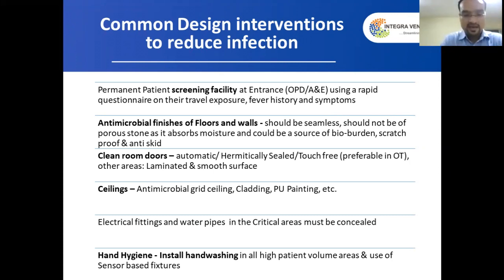Similarly, for ceilings we get a lot of grid ceilings, which are very easy to use. Most high risk areas need a lot of air handling and electrical requirements, so the conduits, ducting, and electrical lines run through the false ceiling. If the false ceiling is of grid type, it can be removed and serviced. But these grid ceilings have to be of antimicrobial property too, and all electrical fittings and water pipes cannot dangle out. Those need to be concealed properly in the critical areas.